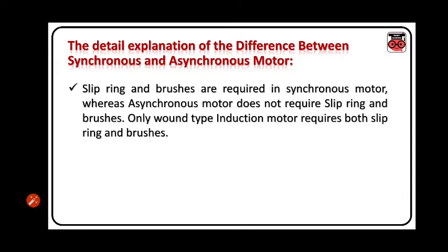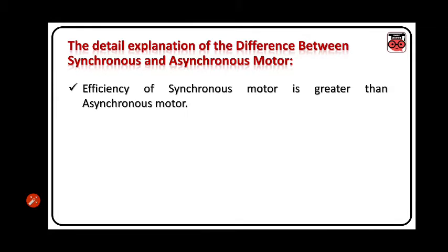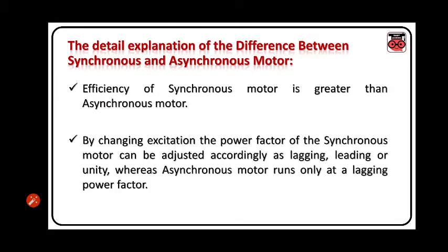Slip ring and brushes are required in synchronous motor, whereas asynchronous motor does not require slip ring and brushes. Note that only wound type induction motor requires both slip ring and brushes. Synchronous motor is costly as compared to the asynchronous motor. Efficiency of synchronous motor is greater than the asynchronous motor. By changing excitation, the power factor of synchronous motor can be adjusted as lagging, leading, or unity, whereas asynchronous motor runs only at lagging power factor.